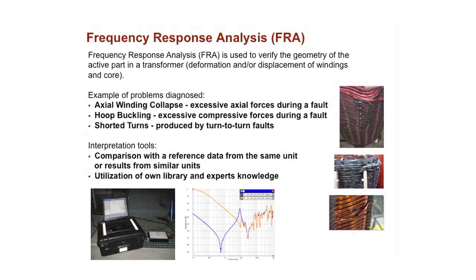Now, when you look at a typical FRA trace, it's more a comparison measurement. So usually you need to have something from before there was a problem, or you can compare to a sister transformer, or you could also compare phase to phase of a transformer. But again, this can be a very good tool to diagnose if there's been an issue with the transformer.